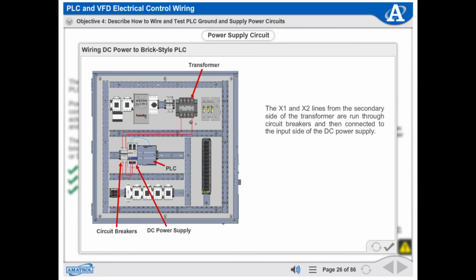The X1 and X2 lines from the secondary side of the transformer are run through circuit breakers and then connected to the input side of the DC power supply. The DC power supply output is wired to the PLC, DC I/O modules, and DC field devices.